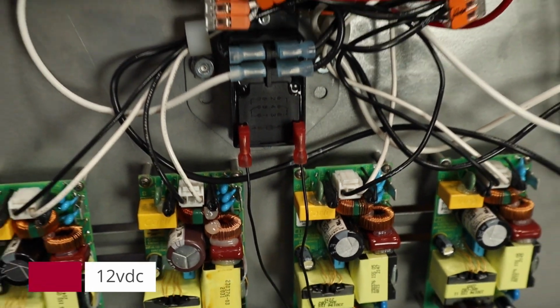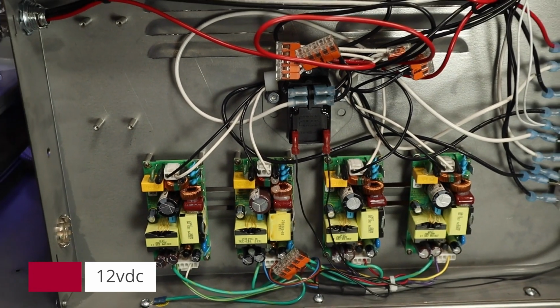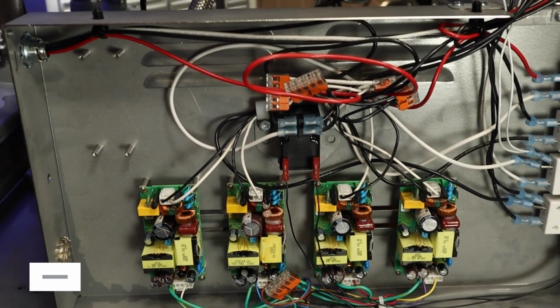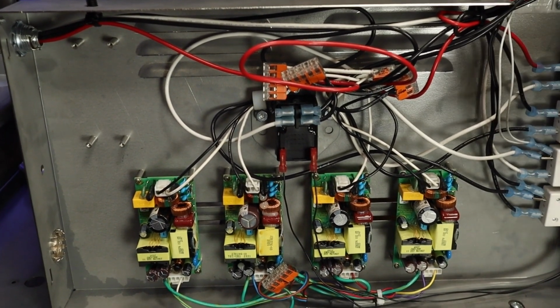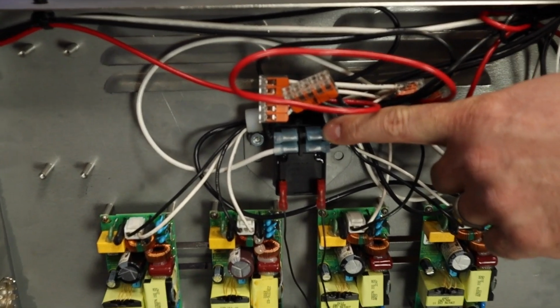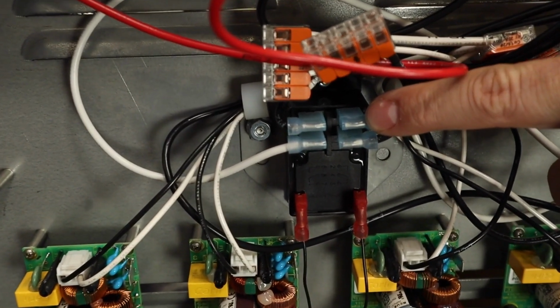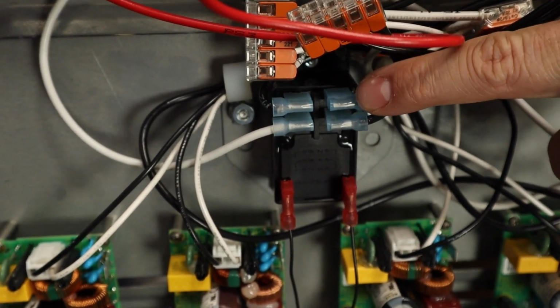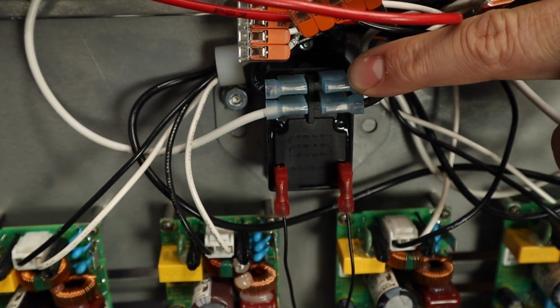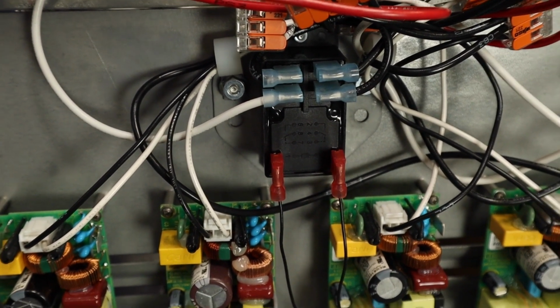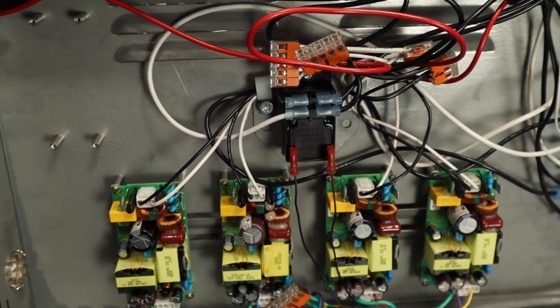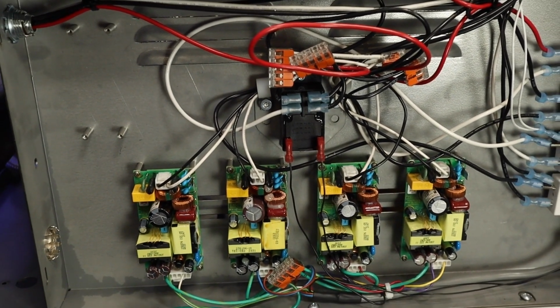Do you remember what voltage we should have right here on the coil for our filter motor relay? Remember, it's 12 volts DC, right here on the bottom 2 terminals. If we have that, then we should have line voltage across the top 2 terminals going out to our filter motor. If not, then we have a bad relay. If we do have that voltage, then we can proceed with checking the voltage at our motor and potentially have an issue with a bad filter motor.